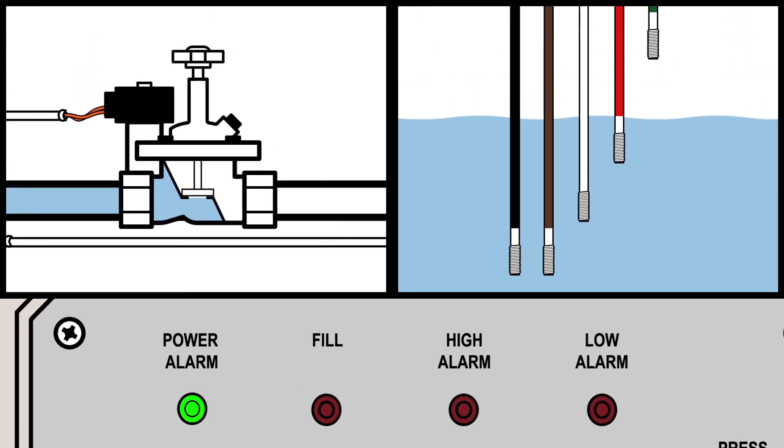Operationally, the valve opens when the water drops below the white rod, and the LED for fill turns on along with the respective relay and dry contact. The valve closes when the water reaches the red sensor rod.